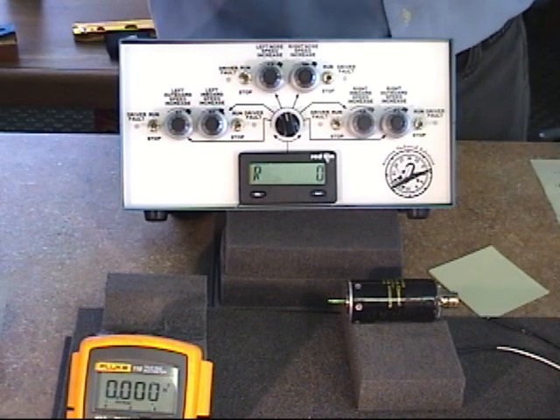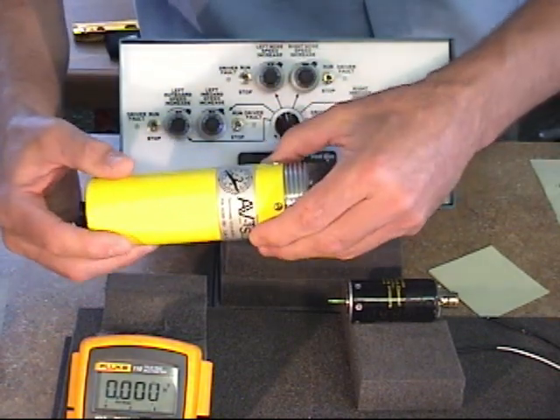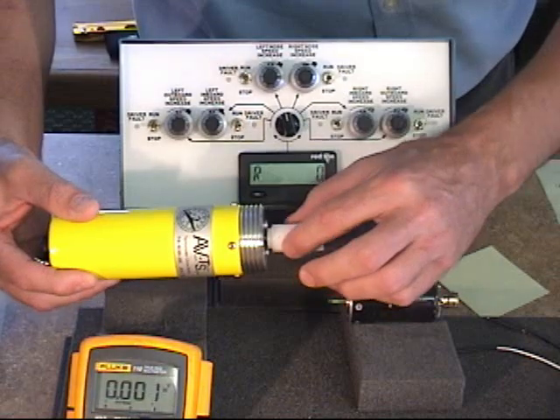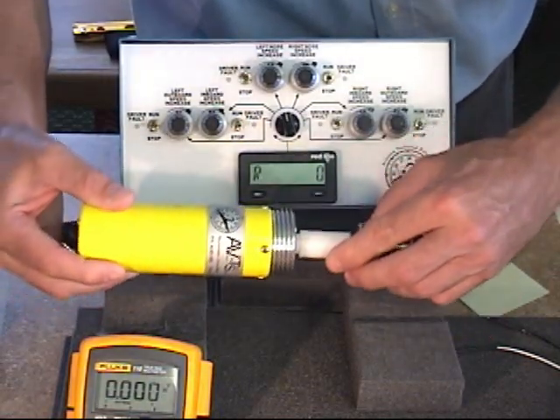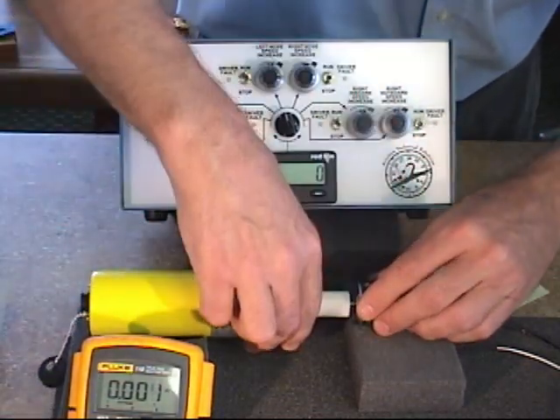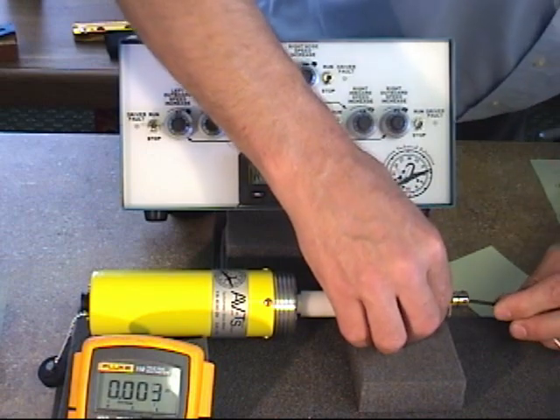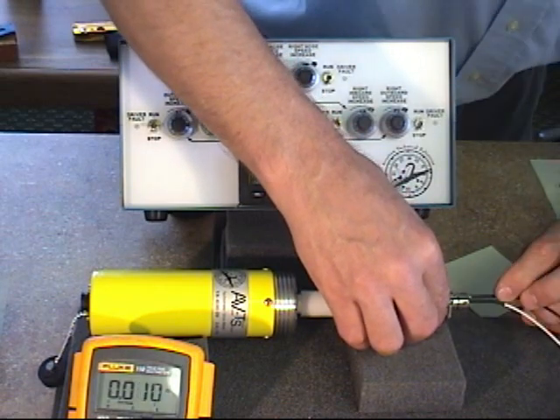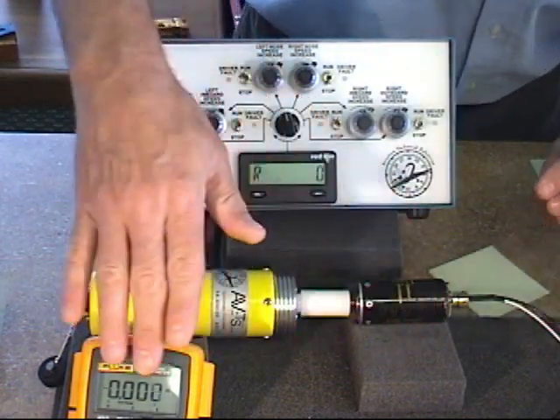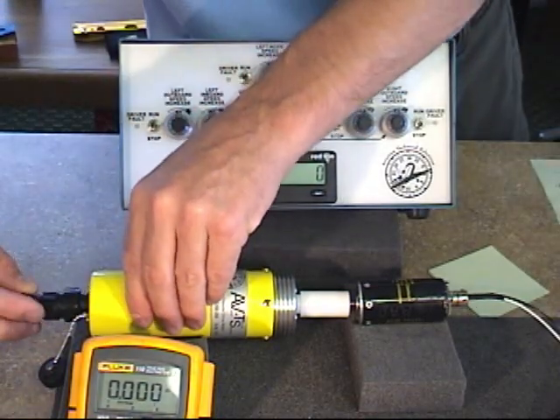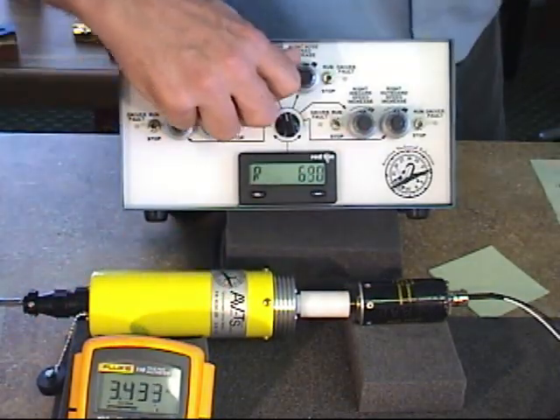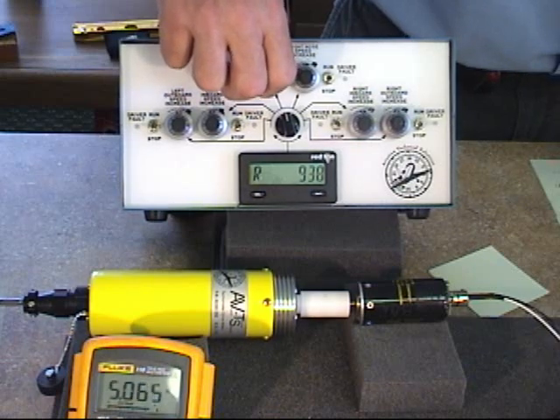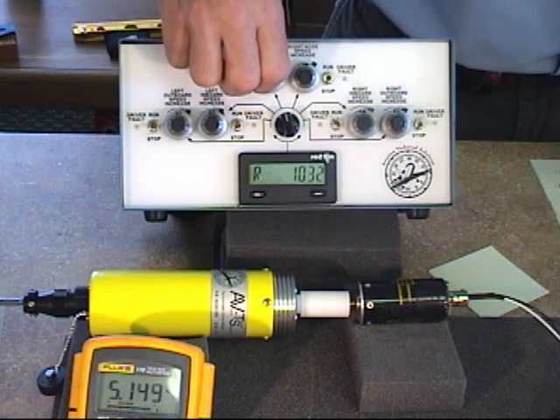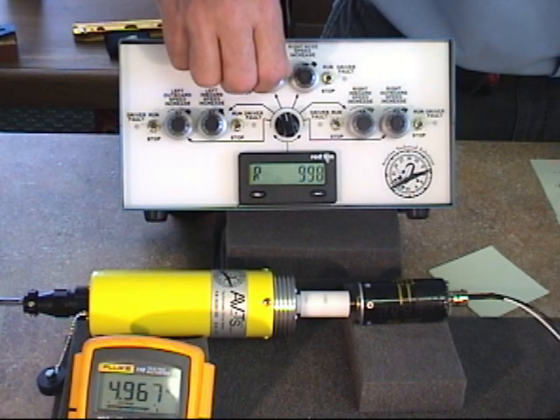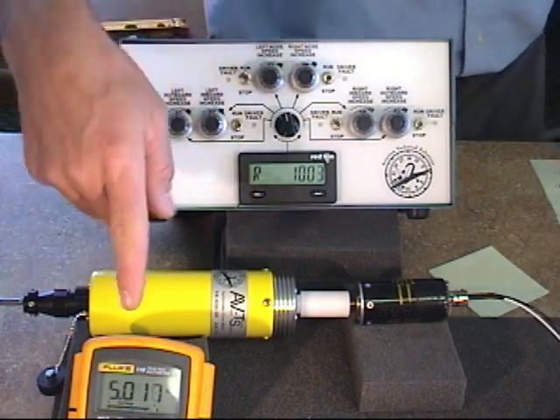Okay, this time we'll do a voltage check. We'll use a single driver off the AS100 system, Falcon 900 drive adapter, and set up with our pin A and C here. Straight test leads, nothing special there. Fluke meter set to volts, and we'll just go ahead and bring this right up to 1000 RPM. And we can do a quick little voltage check. Looks like we're right close to 1000. And we're right on about 5.